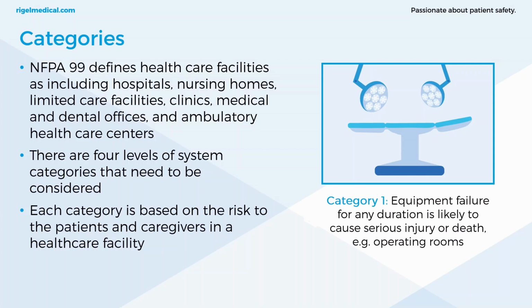Now we will first find in the first few slides of the NFPA 99 code that there are system categories that need to be considered. Now it's up to the facility to define these categories through a risk assessment. So the first category, which has the highest risk, is where equipment failure for any duration is likely to cause serious injury or death. And a good example of this is an operating room.